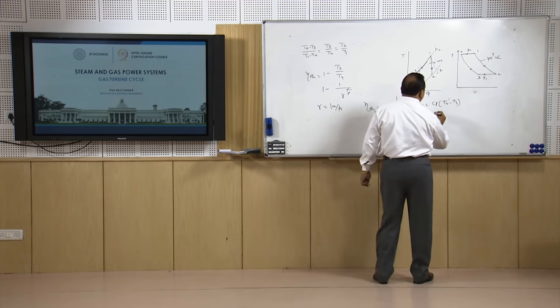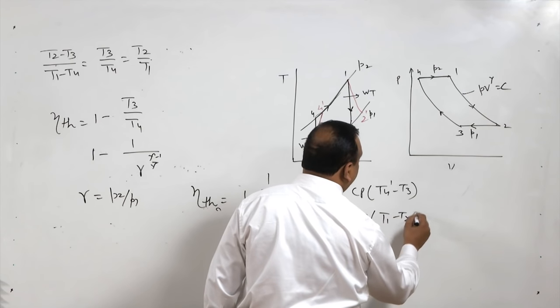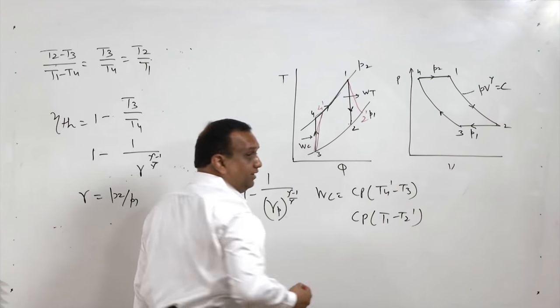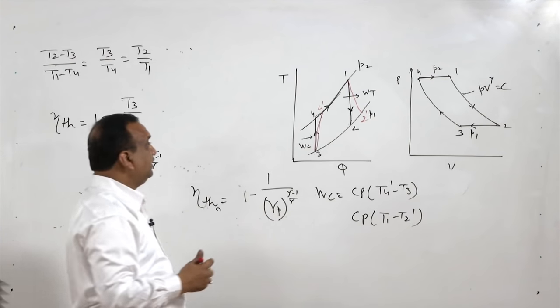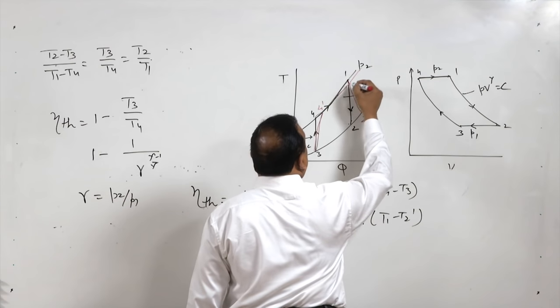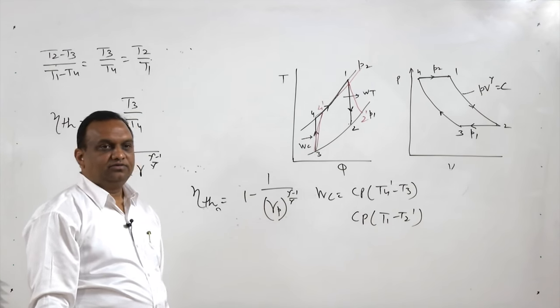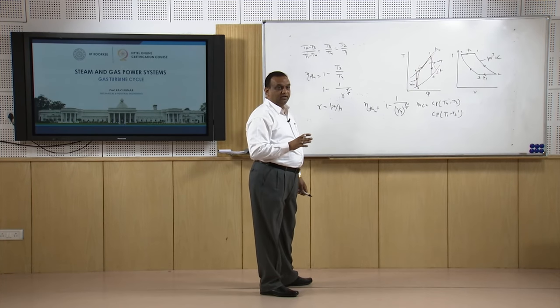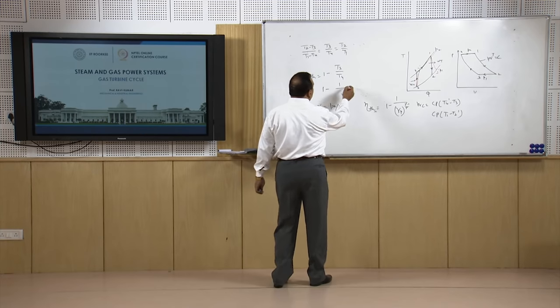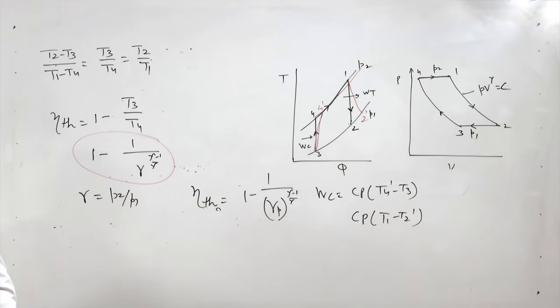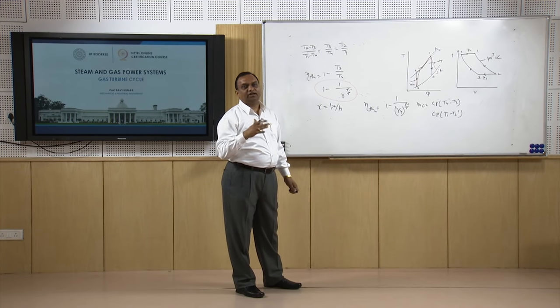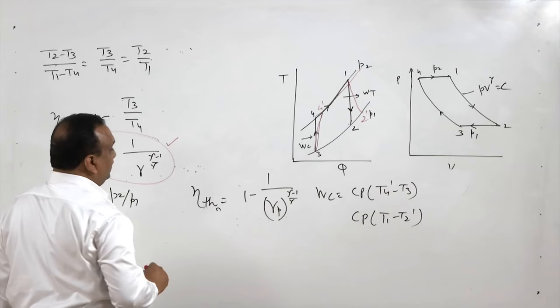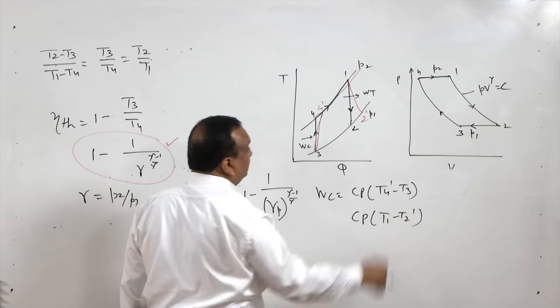Actual work in the compressor is Cp(T4-dash − T3). In the combustion chamber there is also a pressure drop due to flow resistance, so pressure is no longer P2 but slightly less, and expansion starts from a lower point. So the actual cycle deviates quite substantially from the ideal cycle. But we need this air standard efficiency as a baseline for comparing the performance of different turbines.